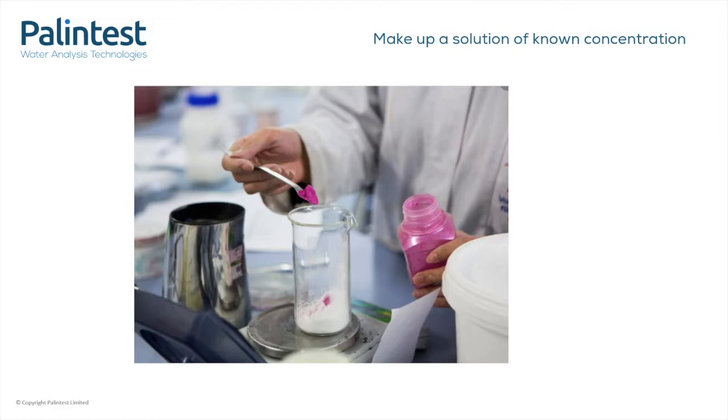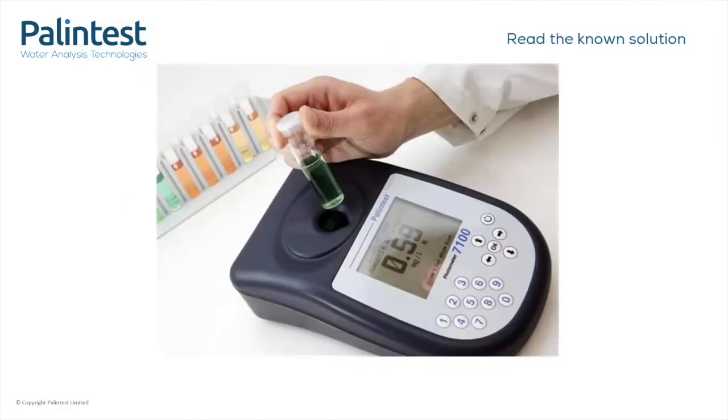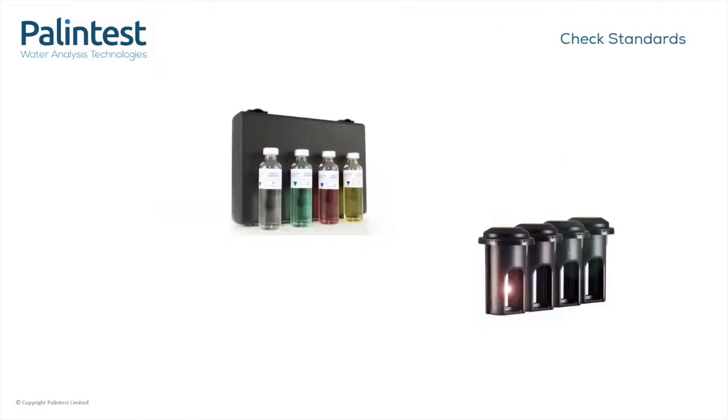However, this is not an easy thing to do. And the result you get on your photometer may tell you how well your photometer is reading, or it may tell you how good you are at making up one milligram per litre solutions of ammonia. The easier option by far is to use check standards.